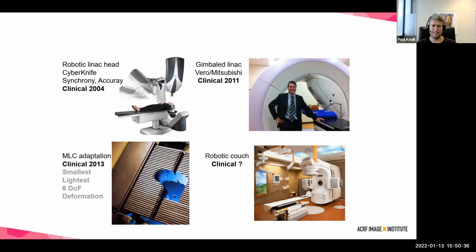That is a tool that we have put a lot of time and effort into for research, development, and clinical application. Each of these leaves is driven by a stepper motor, so we can shape the beam individually with time. And also the couch that the patient lies on hasn't been used clinically, but could be used for this to assist with the targeting.